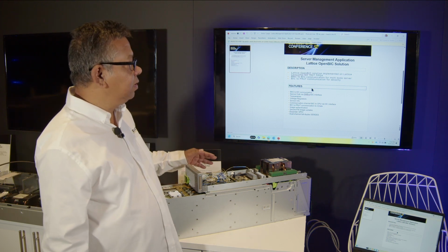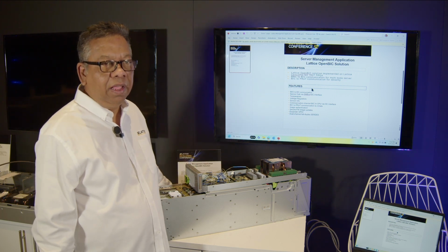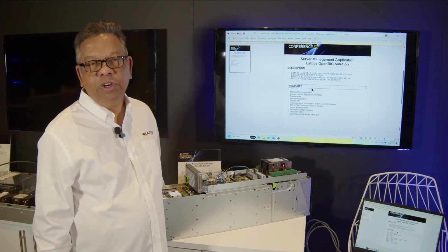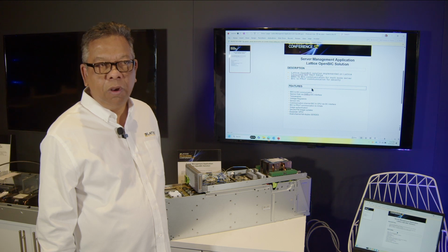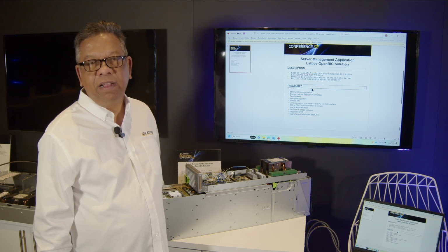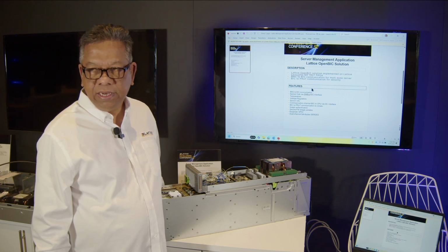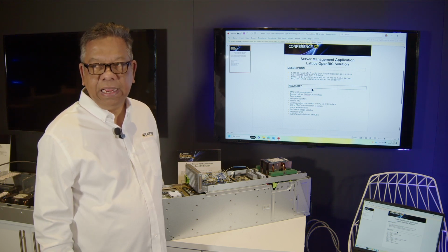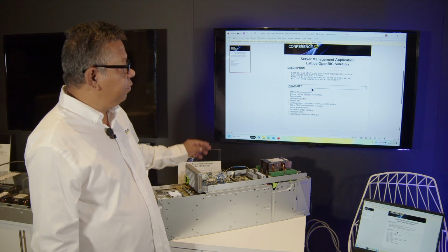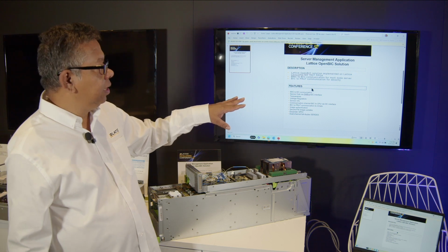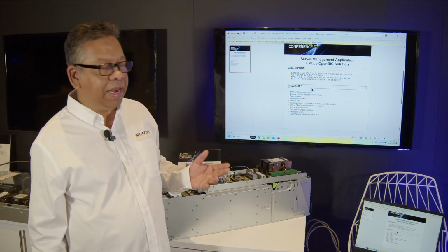This particular one was developed based on the OpenBIC solution that OCP has been driving. BIC typically does temperature monitoring, sensor management, health management, and different logging of the platform. So all the health and management stuff, controlling the fan, looking at the power supplies, the temperature, sensor monitoring, this is what a BIC typically does. Here we did a Lattice OpenBIC solution, which is a server management, a subset of BMC, the baseboard management controller.